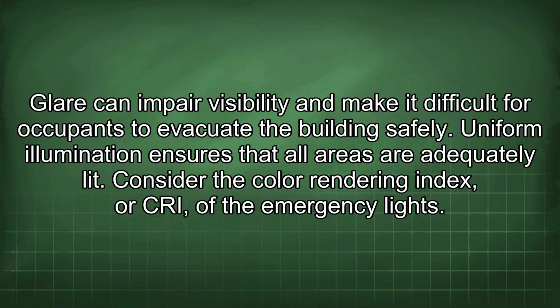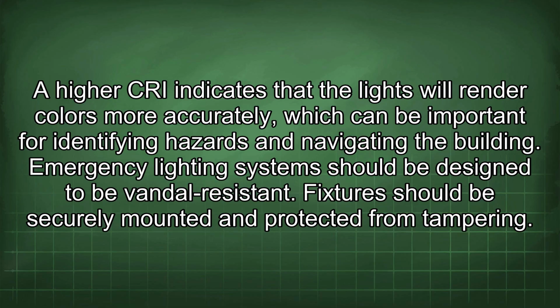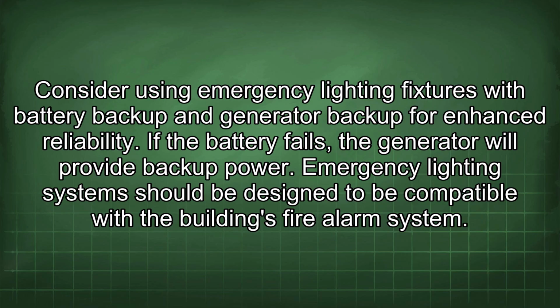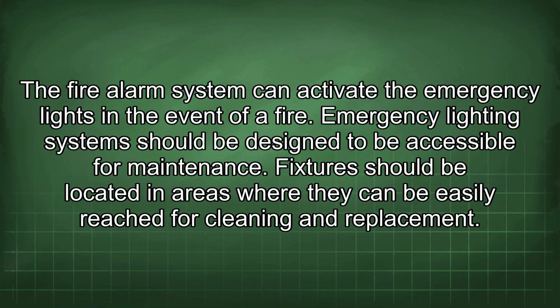Consider the color rendering index, or CRI, of the emergency lights. A higher CRI indicates that the lights will render colors more accurately, which can be important for identifying hazards and navigating the building. Emergency lighting systems should be designed to be vandal resistant. Fixtures should be securely mounted and protected from tampering. Consider using emergency lighting fixtures with battery backup and generator backup for enhanced reliability. If the battery fails, the generator will provide backup power. Emergency lighting systems should be designed to be compatible with the building's fire alarm system. The fire alarm system can activate the emergency lights in the event of a fire.